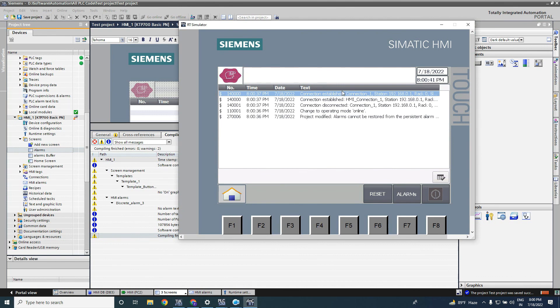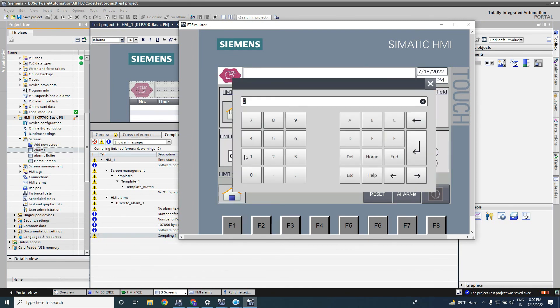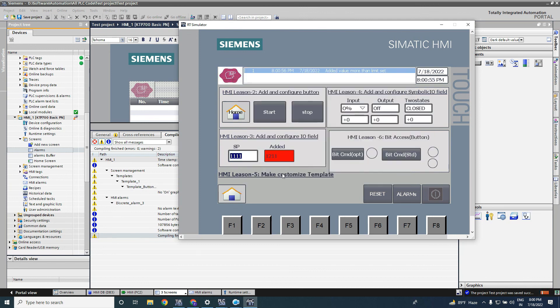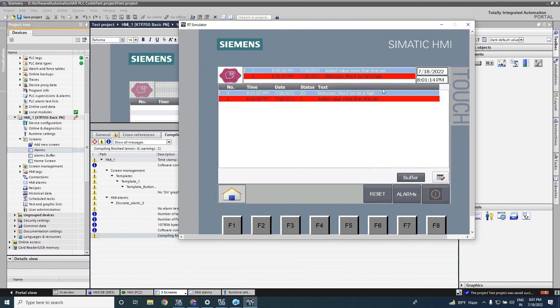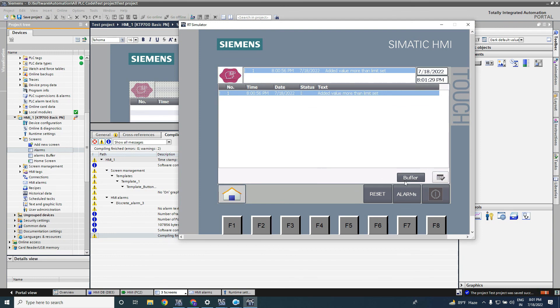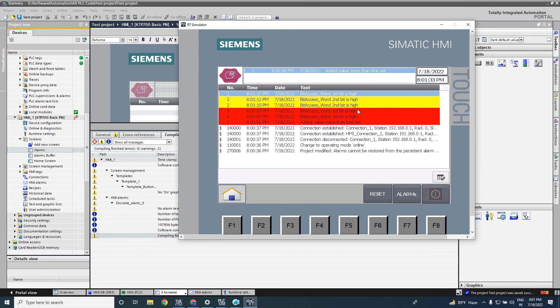To navigate to the alarm buffer page from the alarm page, I will add a button labeled 'buffer' with a click event that changes the screen to the alarm buffer screen. Now simulating the HMI again — if I click, I can go to the alarm buffer page. Going back to the home page, if I give a value more than 300 the 'added value more than limit set' alarm triggers. Going to the buffer page, all alarms are visible there — both current and historical alarms.